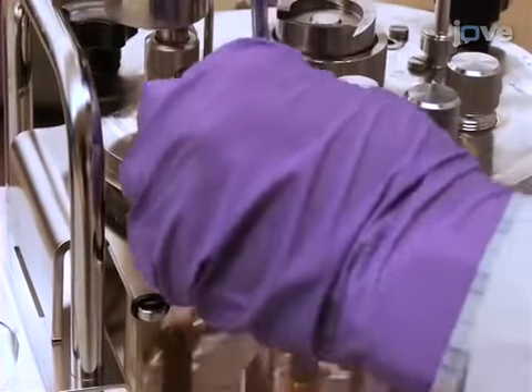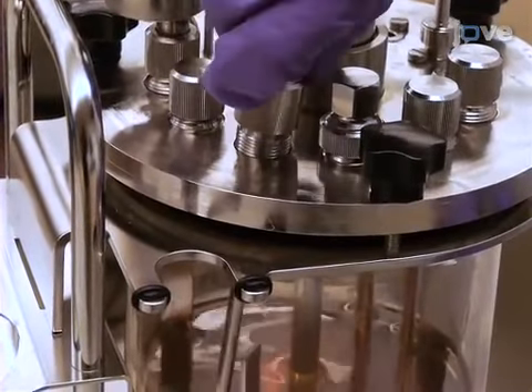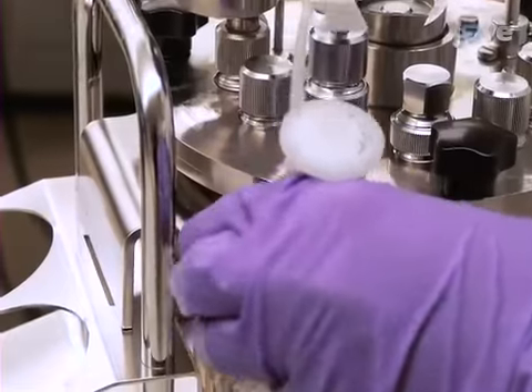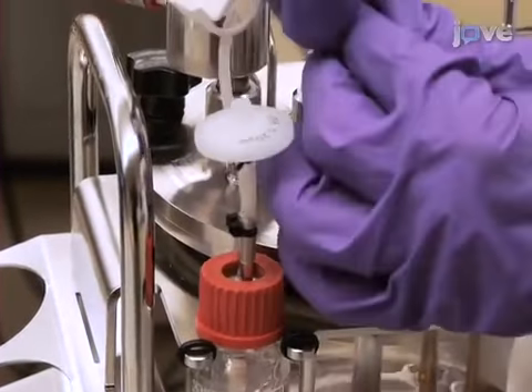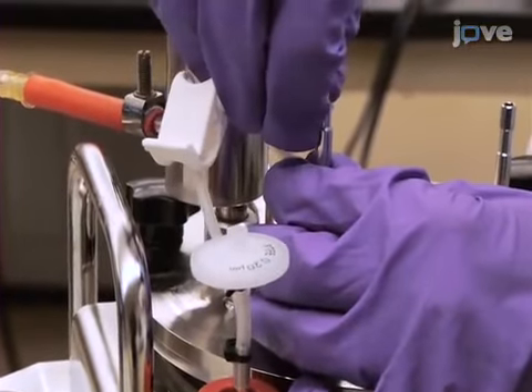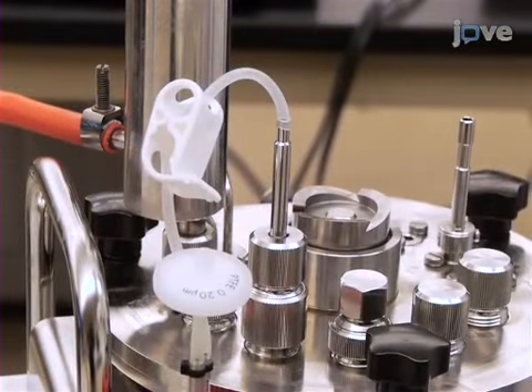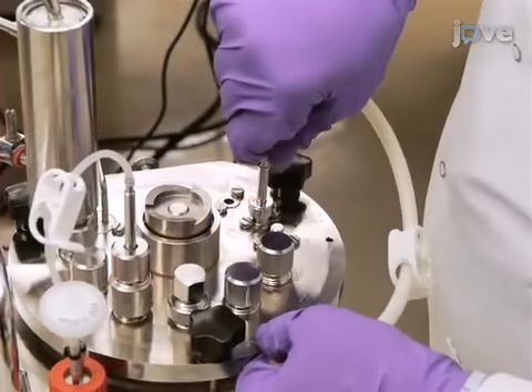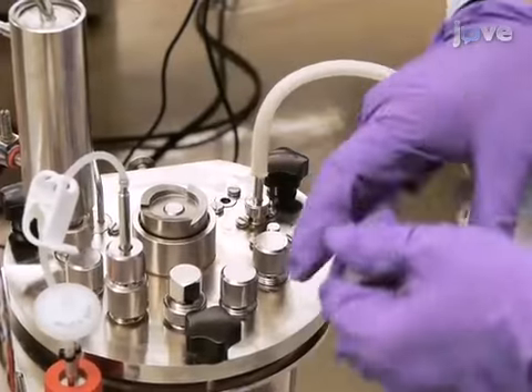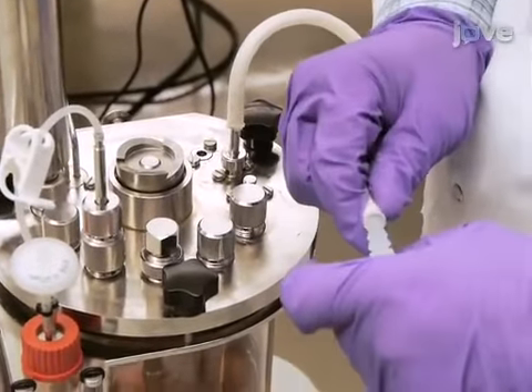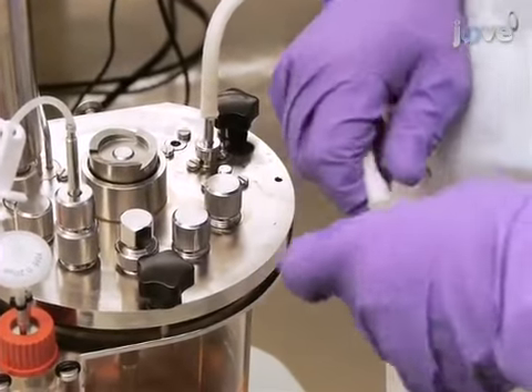Install the harvest pipe into its 10 mm port. Place a piece of tubing on top of it, connect to the sampling bottle, and clamp the tubing off. Install tubing and a 0.2 micron filter on the sparge inlet, and then clamp this off.